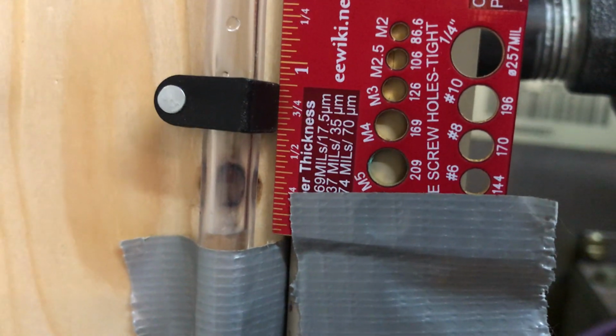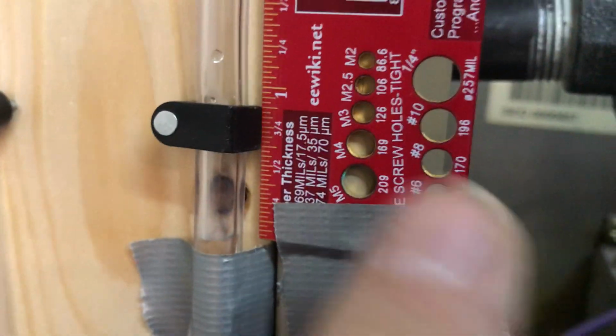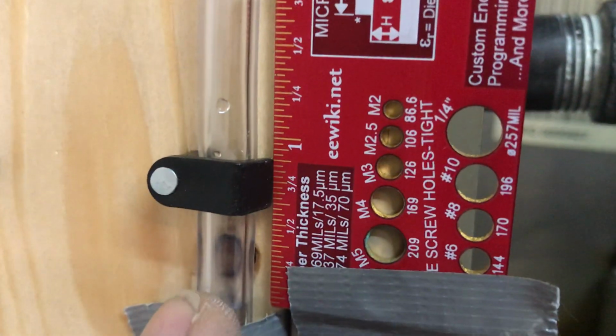And we're going to attempt to measure the water column pressure. The thing is, it's double this. So basically, you measure how many inches the water goes up, and you times it by 2, because it's the increase plus the decrease on the other side. That's how they rate water column pressure. So let's go ahead and turn the furnace on, and we'll see the gas valve in action.